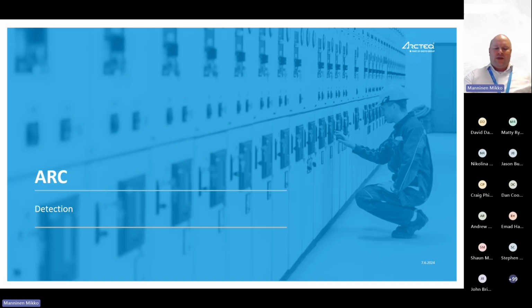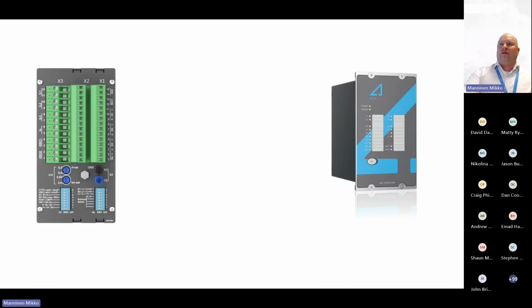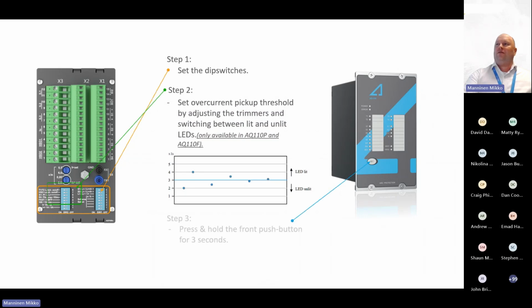Then the 3 steps, the 3 solutions, the 3 applications mentioned before. The first thing is to detect. And there are different ways to detect arc flash. One of them is current. It's the current threshold, inrush current or current threshold during the arc flash. So this is one way to detect. It's not the only way, but it's a part of the detection.